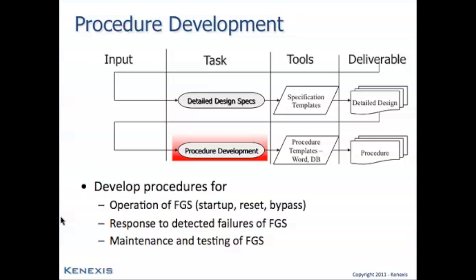So in order to ensure that all the potential repairs can be done, developing the procedures is important, as it will yield requirements for spare parts, staffing, diagnostics annunciation, and cooperation between the maintenance staff and the operations staff. Also, on a periodic basis, the FGS system is going to need to be maintained and tested. Development of those procedures needs to be performed, again, prior to the final design of the system, so that if required, the final design can be modified to meet any unforeseen situations that are created as a result of maintenance and testing requirements.